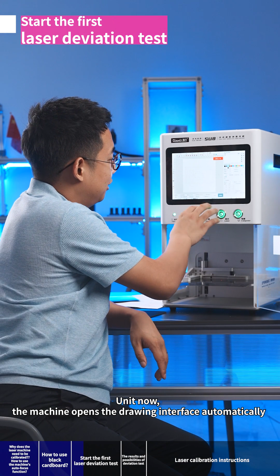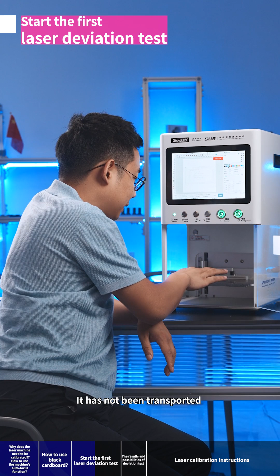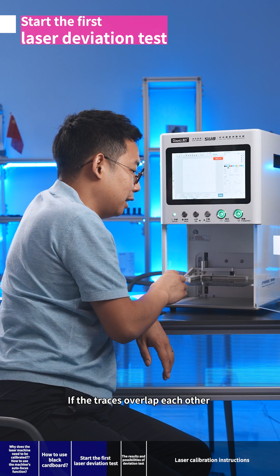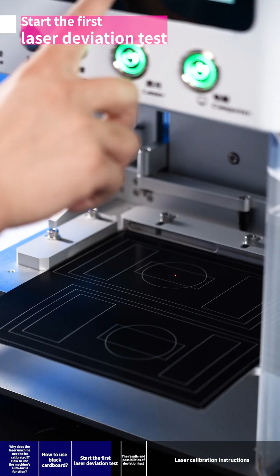Why do we mark? What's the principle? Let me tell you about it. Before the machine leaves the factory, it has not been transported. The cardboard was put here to mark, and then the cardboard was put in the package. After transportation, put the same cardboard in the same position and follow the same procedure to laser on it. If the engraved traces overlap, it means the machine is fine. If not, that means the optical device of the machine is deviated. That's the reason we need to calibrate it. If the traces overlap each other, we can use the machine directly. No need to calibrate. Now let's try to mark and see if the new traces overlap the factory traces.